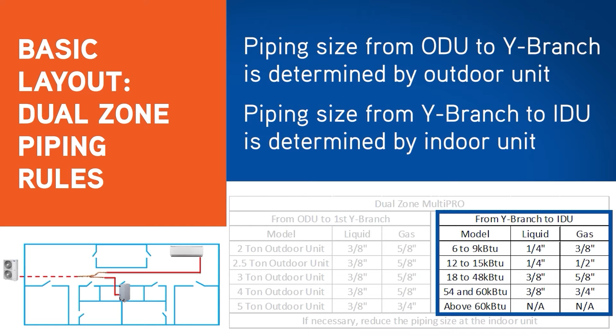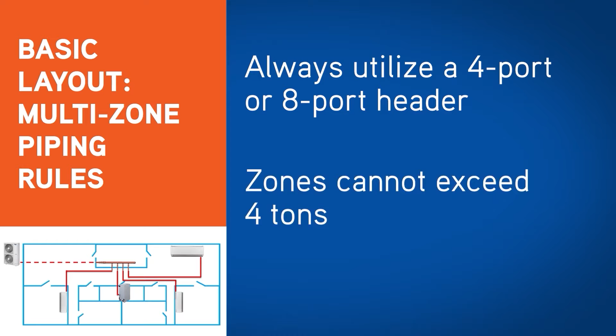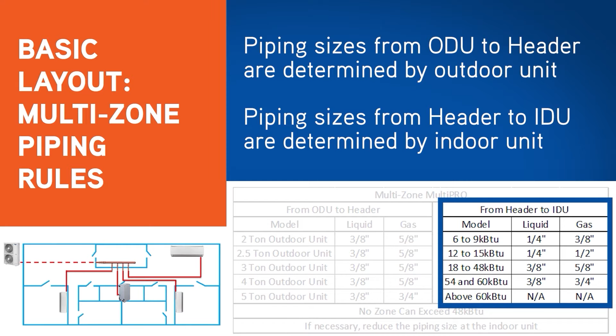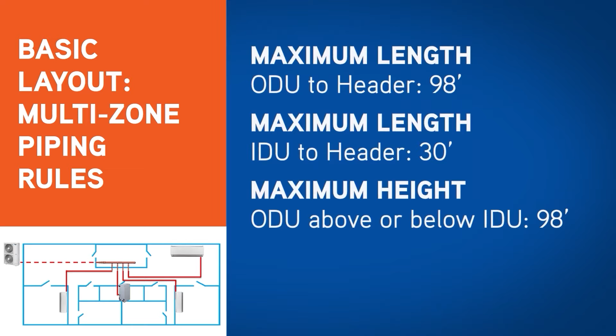Even at its most complex, the multi-zone MultiPro basic layout is still simple with easy to follow rules. This layout will always utilize a 4-port or 8-port header. Each zone cannot exceed 4 tons. As before, the piping size from the outdoor unit to the header is determined by the capacity of the outdoor unit. The piping sizes from the header to the indoor units are determined by the indoor unit capacity. The piping length limitations are the same as the dual zone basic layout.